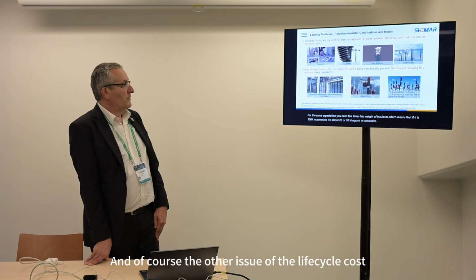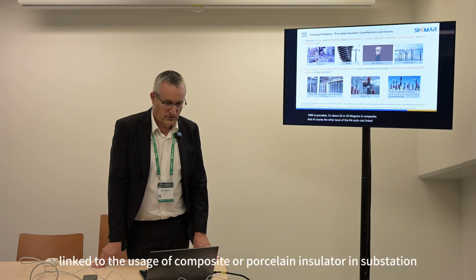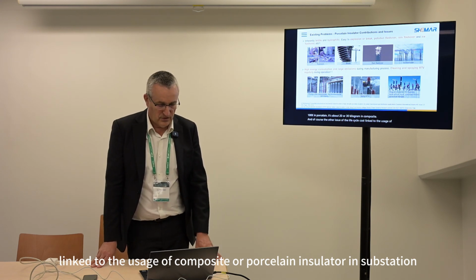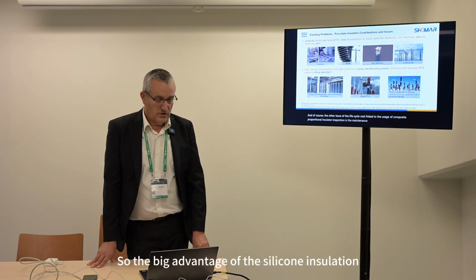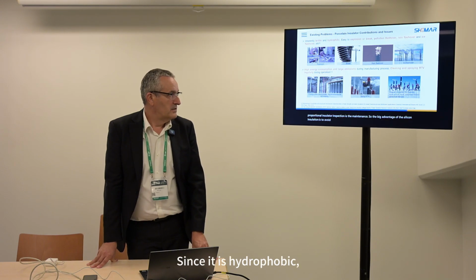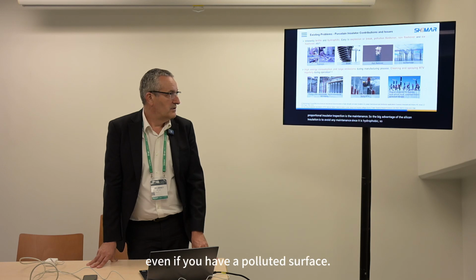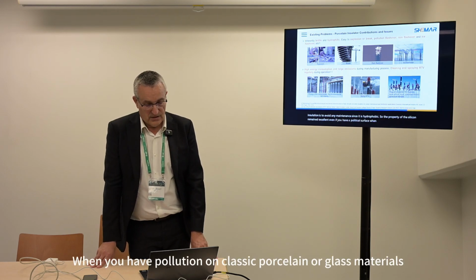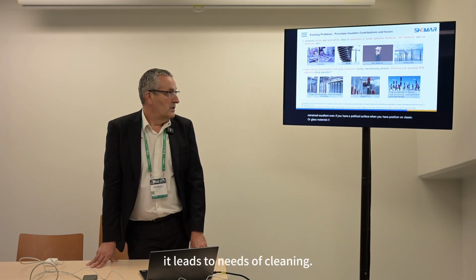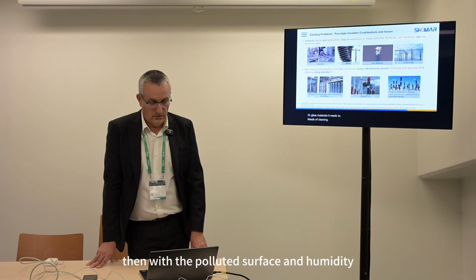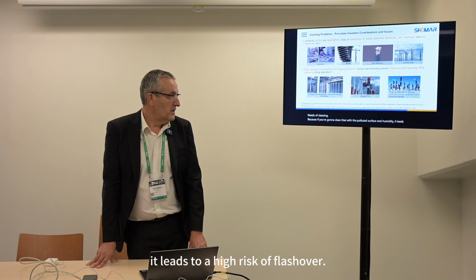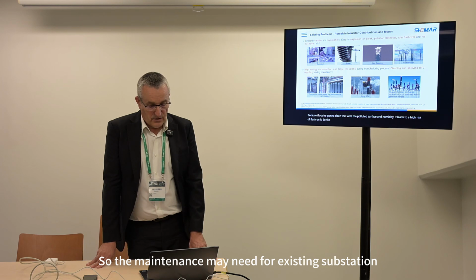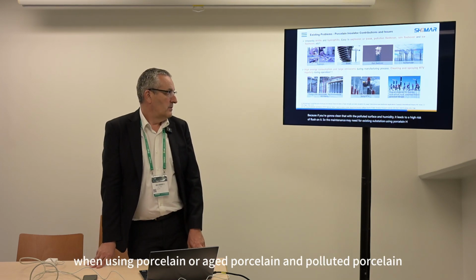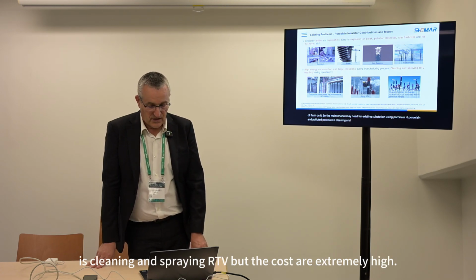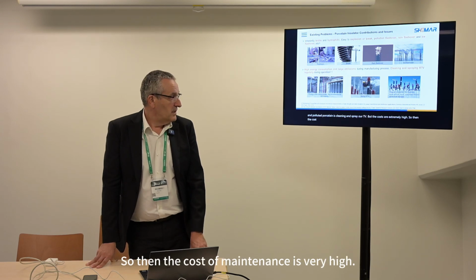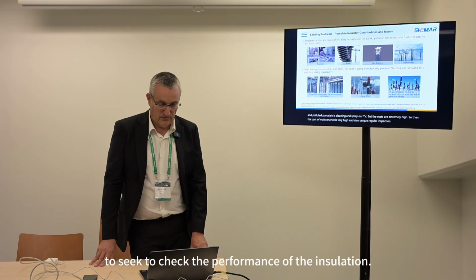And of course, the other issue of the life cycle cost linked to the usage of composite or porcelain insulators in substations is maintenance. The big advantage of silicone insulation is that it avoids any maintenance, since it is hydrophobic, so the property of the silicone remains excellent even if you have a polluted surface. When you have pollution on classic porcelain or glass materials, it leads to a need for cleaning, because if you don't clean, then with the polluted surface and humidity, there is a high risk of flashover. So the maintenance needed for existing substations using porcelain, or aged and polluted porcelain, is cleaning and spraying RTV, but the costs are extremely high. The cost of maintenance is very high, and you also need regular inspection to check the performance of the insulation.